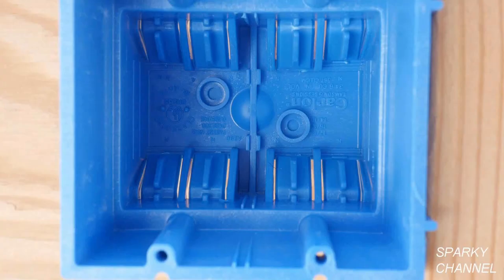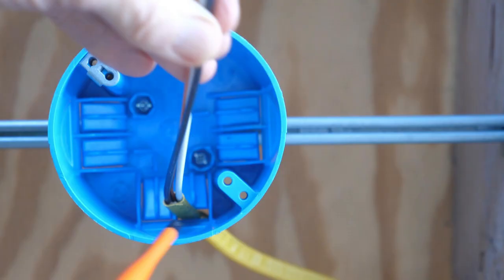And here we are pretty much right back where we started from with a plastic box that has integral clamps, except that it's a 4x4 square box instead of a round box. But it has the same question. Are these clamps to be counted in box fill calculations? In my prep work for doing this video, I found that about 50% of people on the internet in general think that these integral clamps should be counted as box fill, and about 50% think they shouldn't be.